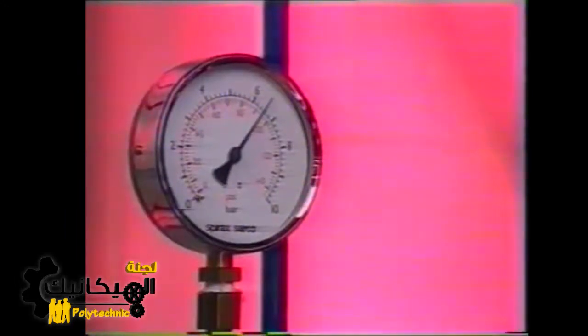Falling pressure has a major effect inside a boiler. Watch as the steam demand is temporarily increased, but within the boiler's maximum output capability. The bubbling water surface begins to rise with surprising speed. And within a few seconds, the level is so high that water and foam are being drawn into the steam takeoff. As soon as the high demand moderates, the pressure rises, and the surface level quickly returns as normal operation is re-established. This sudden response, often referred to as swell, is the result of two compounding factors.